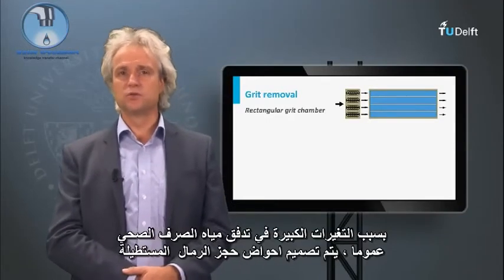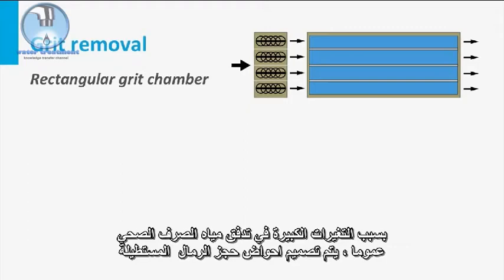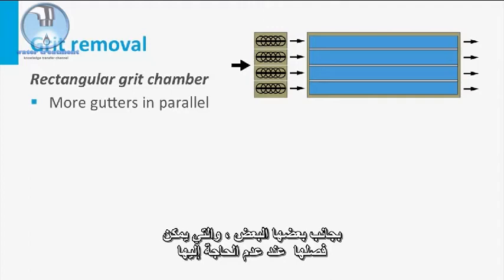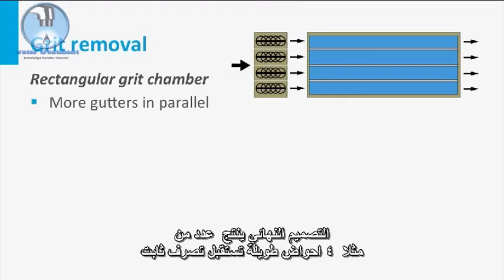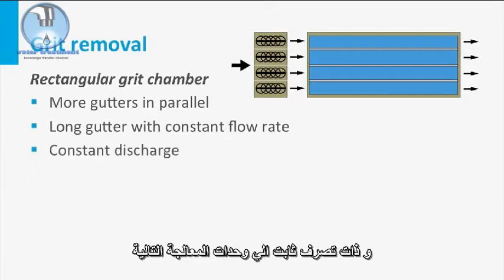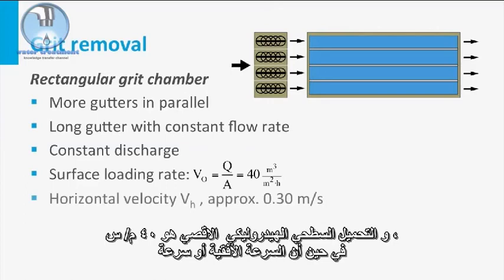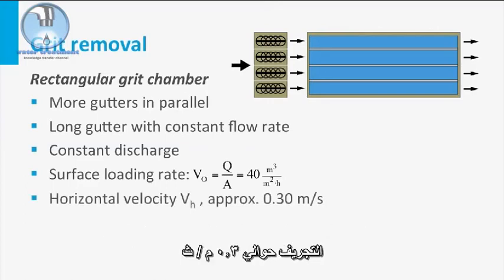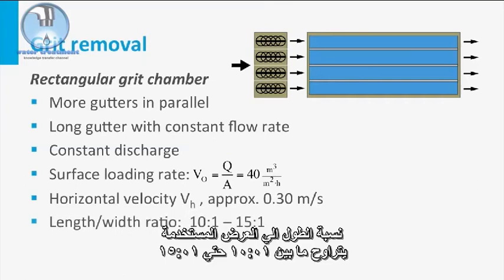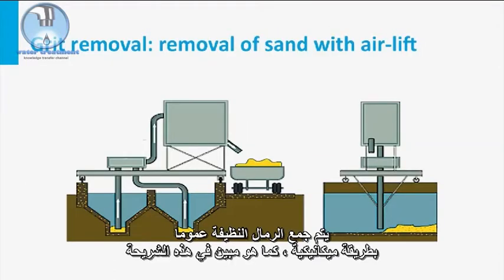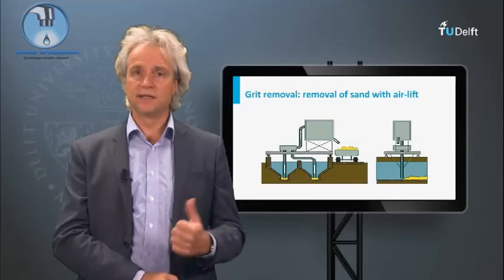Owing to the high variations in sewage flow, generally various rectangular grit chambers are designed next to each other, which can be disconnected when not needed. The final design results in a number of, for instance, 4 long gutters receiving a constant flow rate and having a constant discharge to the next process units. The maximum hydraulic surface load is 40 meters per hour, whereas the horizontal scouring velocity is approximately 0.3 meters per second. The generally applied length-to-width ratio ranges between 10:1 and 15:1. The clean sand is generally collected in a mechanized way, as indicated in this slide.